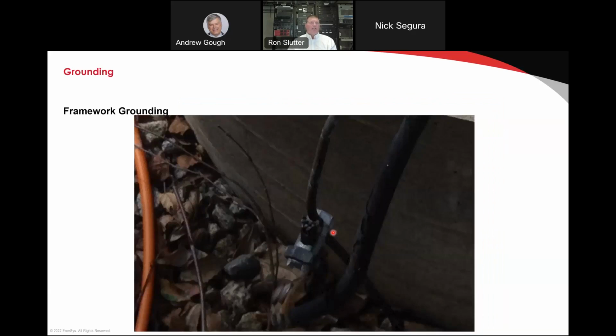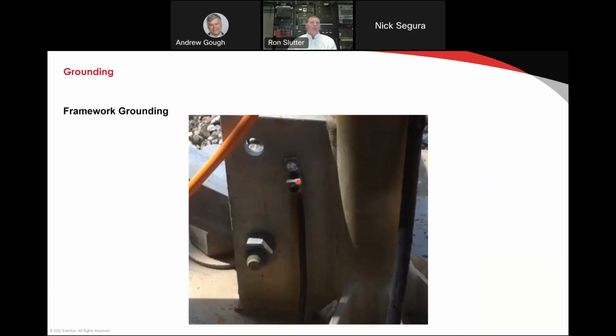Here's an exterior connection. This is a split bolt. This will never work. I tested this. This had 220 ohms of resistance between this conductor and this one. Although it's bolted together, it does not have continuity between the two sufficient to get rid of a significant surge. Here you can see a mechanical lug that's connected to a tower, right? Once again, this had more than 300 ohms of resistance between this conductor. Looks like it's grounded, but it's not working. You have to do testing to know what's going on.